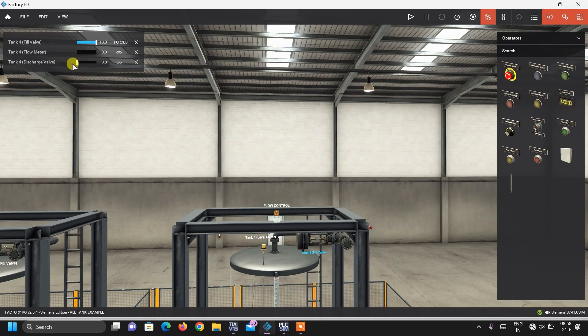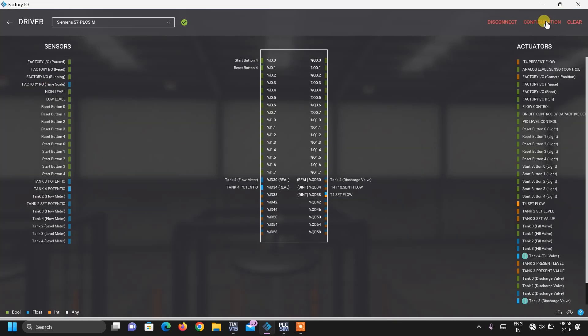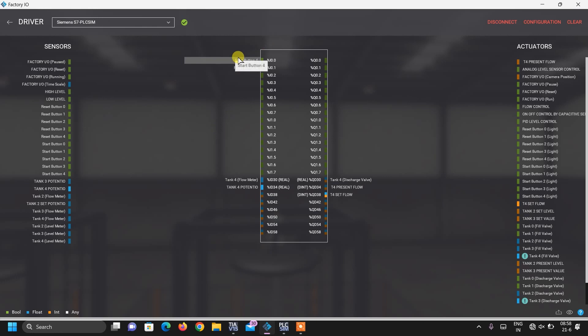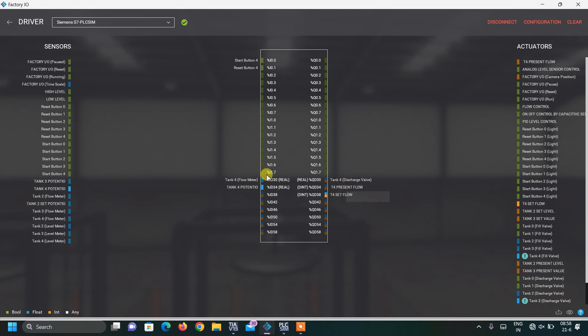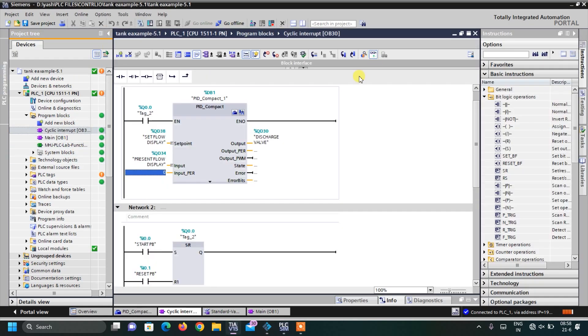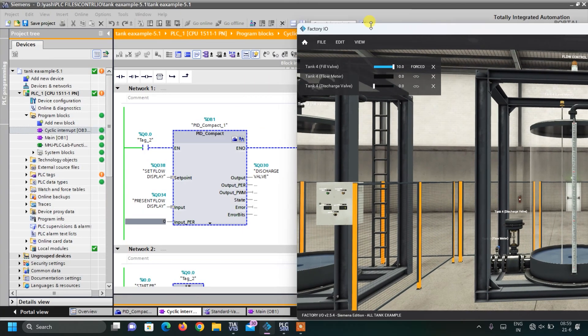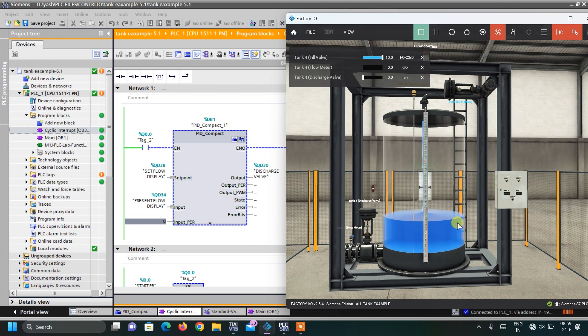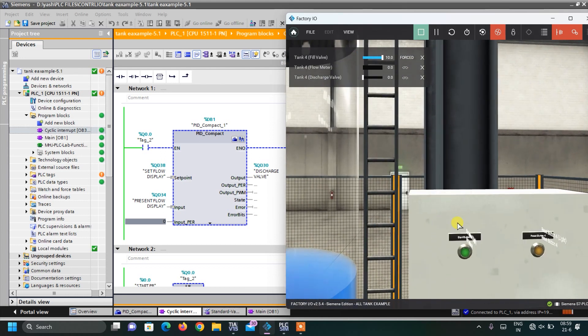I have already downloaded the program. For your setup, change the PLC type to S7-1500, download, then run, and connect to Factory IO. In Factory IO configuration, change to S7-1500 as well. I have connected: start button and reset button, flow meter at ID30, potentiometer at ID34, discharge valve at QD30. The displays are connected at QD34 and QD38 for present flow and set flow. I have also got online and can monitor inputs and outputs.